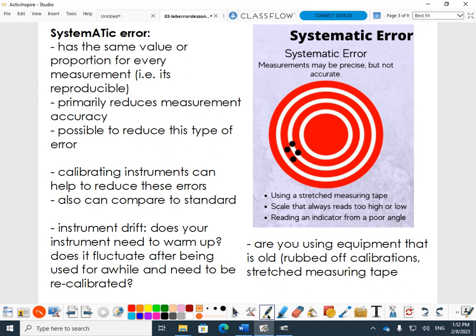This morning I did some measurements and it was all good, and then all of a sudden the last digit started to flicker: 99.355, 356, 357. It started to really change. So if that starts to happen, maybe I turn it off and turn it back on. You have to recalibrate.